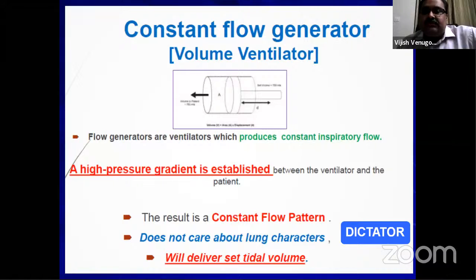We have constant flow generators. Constant flow generators are ventilators that produce constant inspiratory flow. A high pressure gradient is established between the ventilator and the patient, and there is a constant flow pattern. But it does not care about the lung characteristics. So it will deliver the set tidal volume irrespective of the condition of the lung. So this constant flow generator behaves like a dictator.